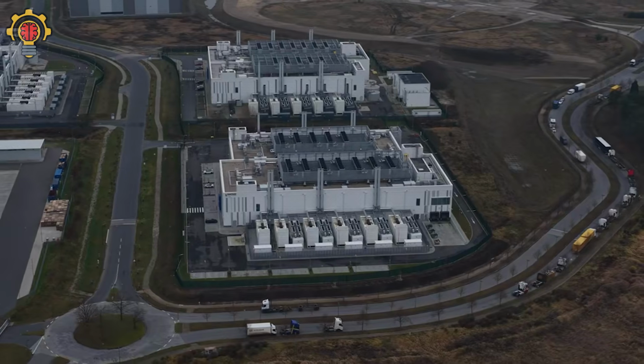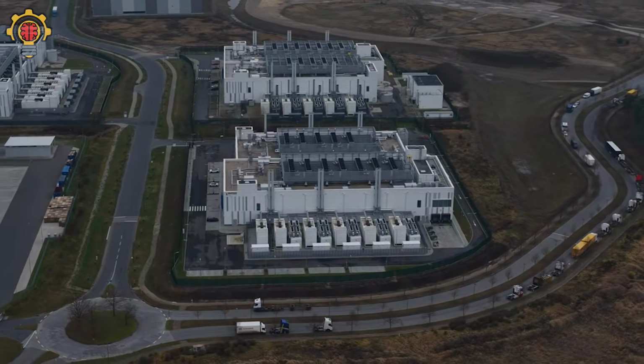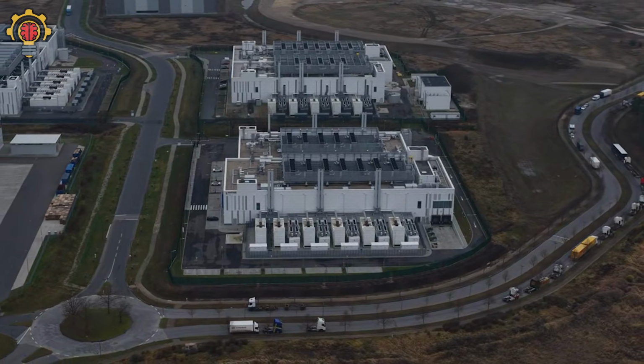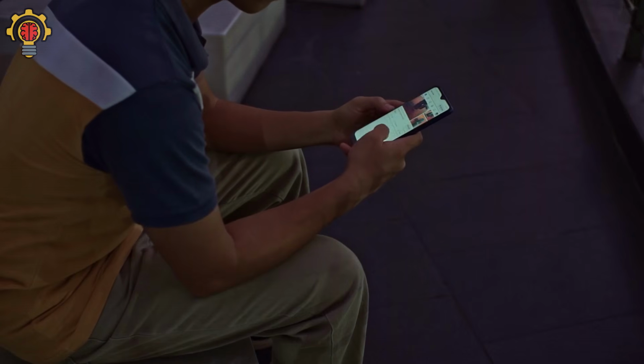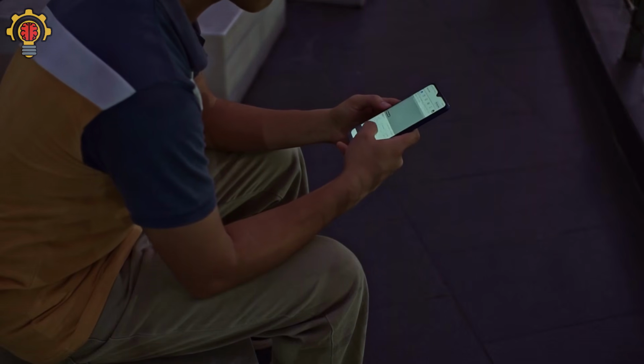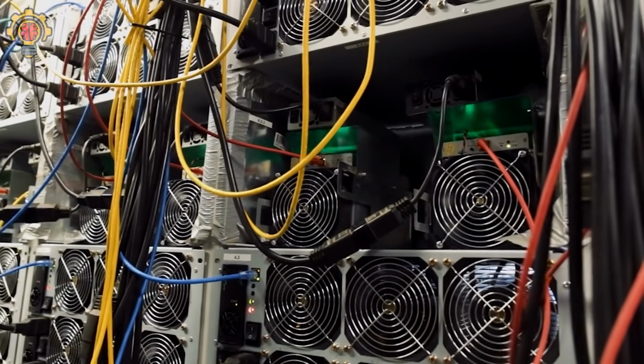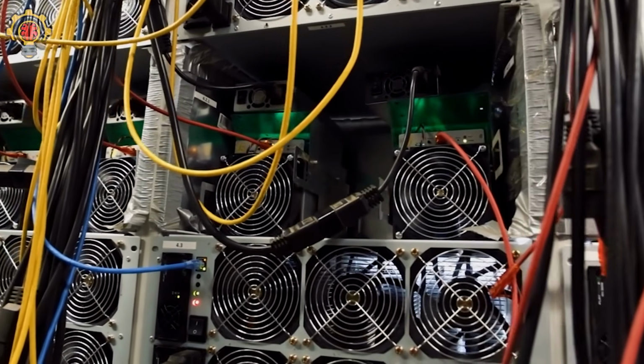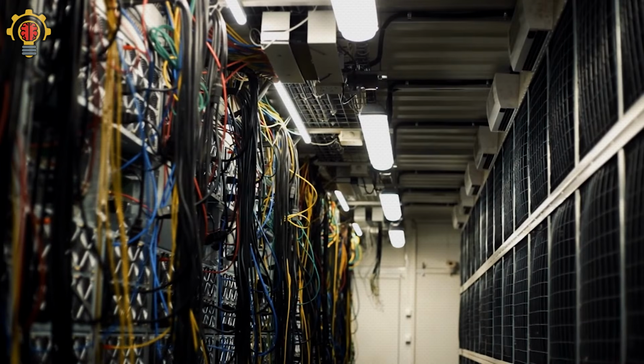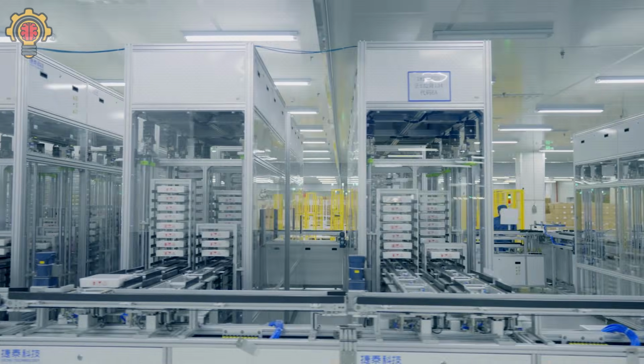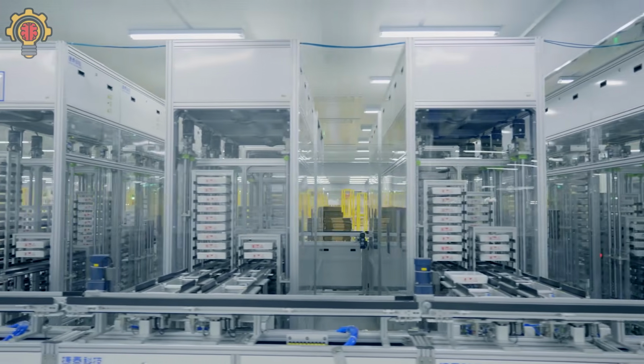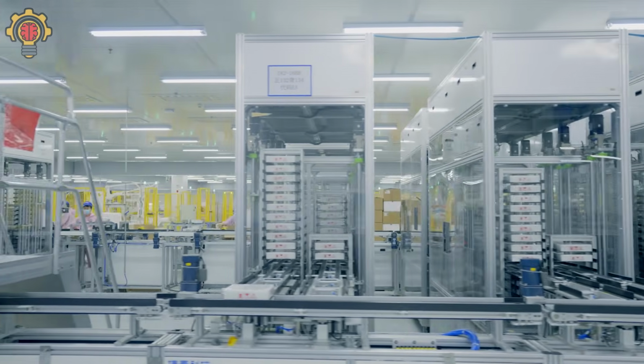But here's the crazy part. The biggest problem inside those buildings is not power, it is heat. A single human sitting in a chair gives off around 400 to 450 BTU per hour, but one server rack inside a data center can produce 17,000 to more than 102,000 BTU every single hour. That is like placing industrial heaters inside a sealed room and never turning them off.